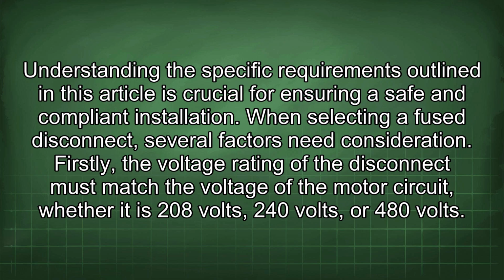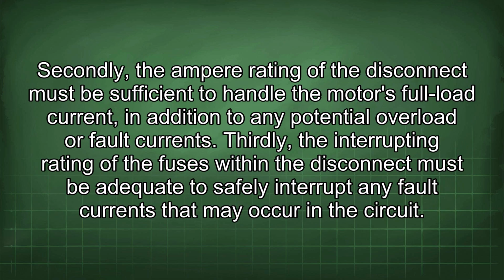When selecting a fused disconnect, several factors need consideration. Firstly, the voltage rating of the disconnect must match the voltage of the motor circuit, whether it is 208 volts, 240 volts, or 480 volts. Secondly, the ampere rating of the disconnect must be sufficient to handle the motor's full load current, in addition to any potential overload or fault current. Thirdly, the interrupting rating of the fuses within the disconnect must be adequate to safely interrupt any fault currents that may occur in the circuit.